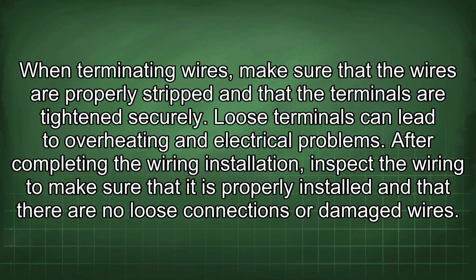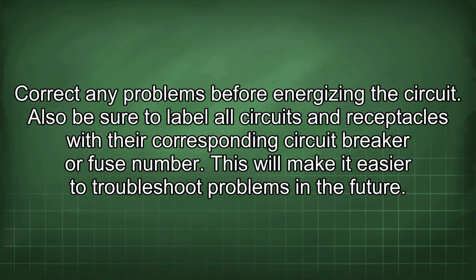After completing the wiring installation, inspect the wiring to make sure that it is properly installed and that there are no loose connections or damaged wires. Correct any problems before energizing the circuit. Also be sure to label all circuits and receptacles with their corresponding circuit breaker or fuse number. This will make it easier to troubleshoot problems in the future.